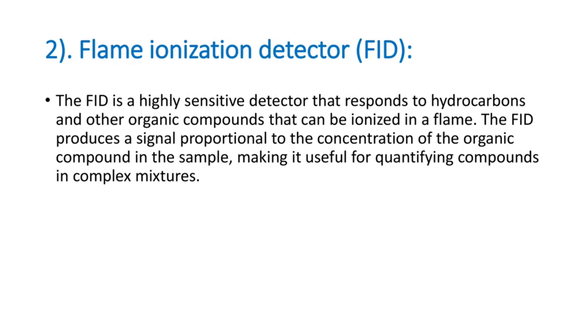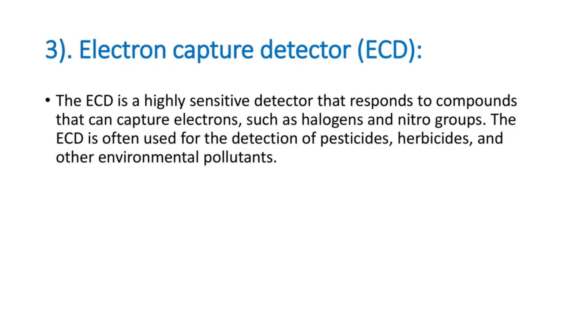Second, flame ionization detector, FID. The FID is a highly sensitive detector that responds to hydrocarbons and other organic compounds that can be ionized in a flame. The FID produces a signal proportional to the concentration of the organic compound in the sample, making it useful for quantifying compounds in complex mixtures.